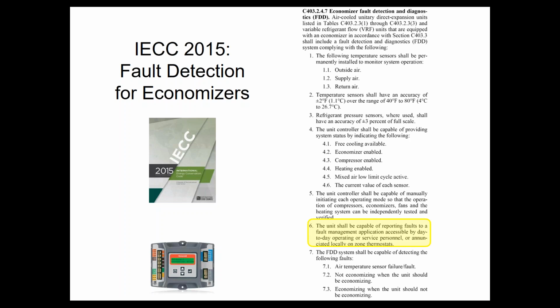The unit shall be capable of reporting faults to a fault management application accessible by day-to-day operating or service personnel. Generally speaking, that means a building automation system. Some people have tried to argue, oh, the economizer controller itself has the alarm, so we're good. Well, first of all, the economizer controller is in the rooftop unit up on the roof. That is not accessible to day-to-day personnel.